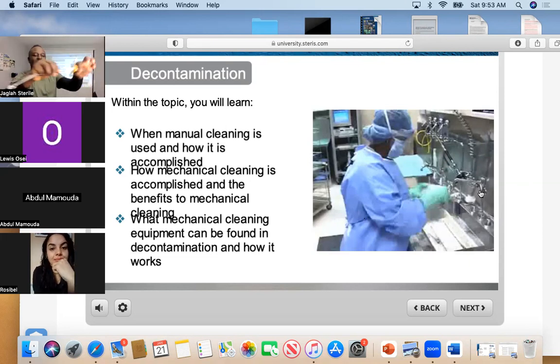In this case, with this brush, you clean it this way underwater, right? If it is bloody, the white brush will change color, so you know it's bloody and you pay attention to it. Rinse it off underwater like this, or just use your glove to remove it, because if I push blood out, I can't pull it back in without cleaning the blood off it. You are recontaminating the equipment. So always make sure when you push a brush through a cannulated item and you see blood, rinse it off before you pull the brush out. Do that like 3 times to make sure you get rid of everything.